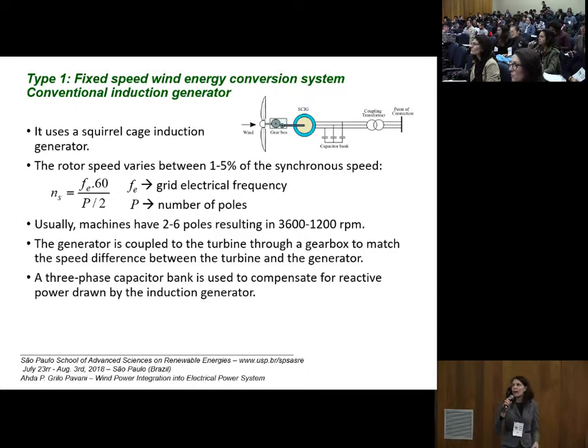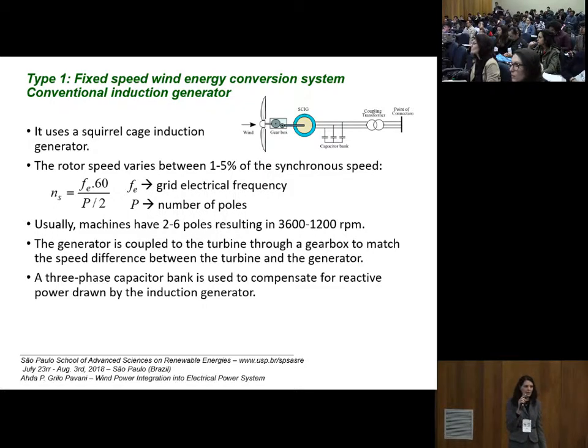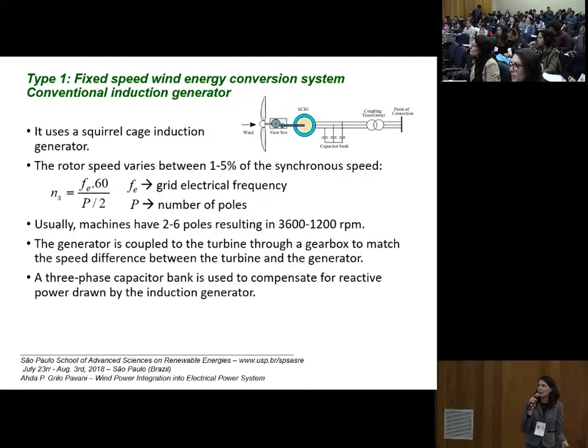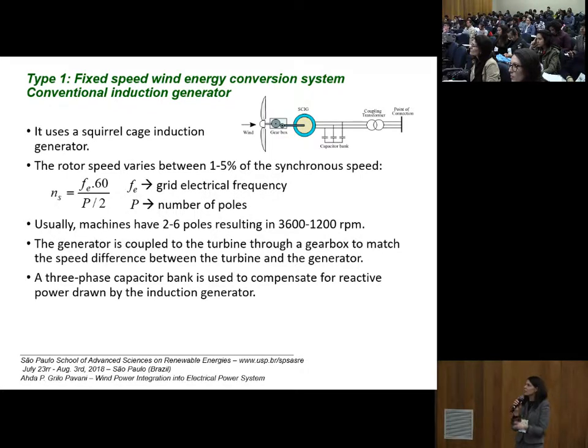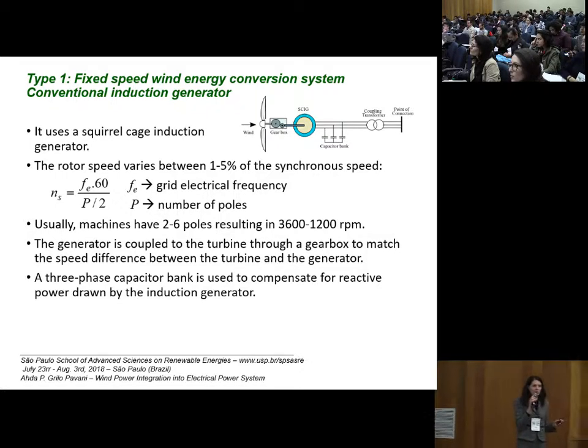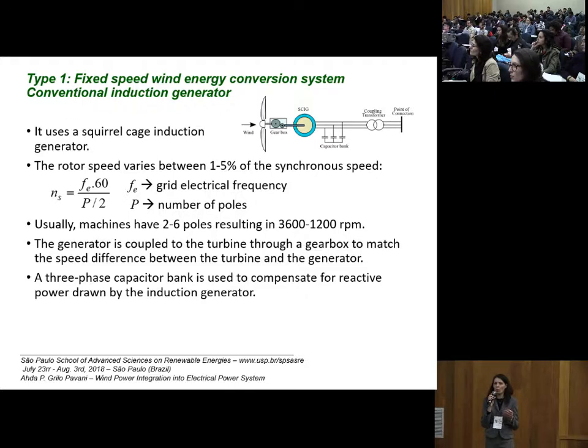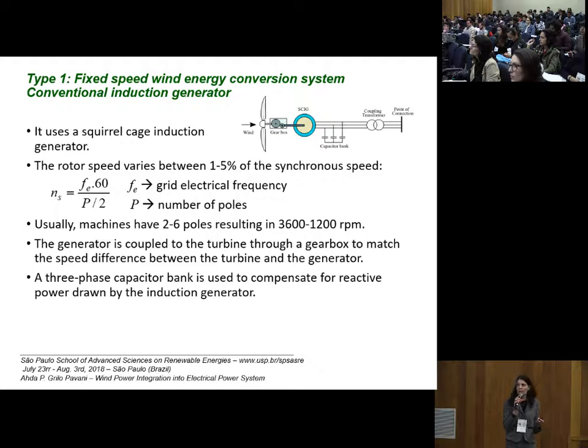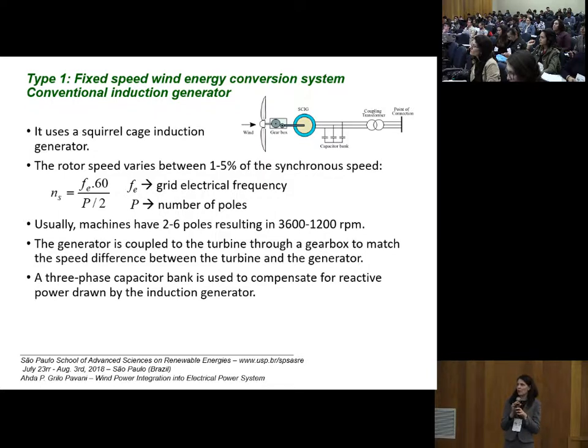The first type of wind energy conversion system is the fixed speed. It uses a conventional induction generator — specifically a squirrel cage induction generator — to convert mechanical energy to electrical energy. The rotor speed of a squirrel cage induction generator usually varies between 1% to 5% of the synchronous speed, which depends on the number of poles of the electrical machine and the electrical frequency, as shown in the equation.